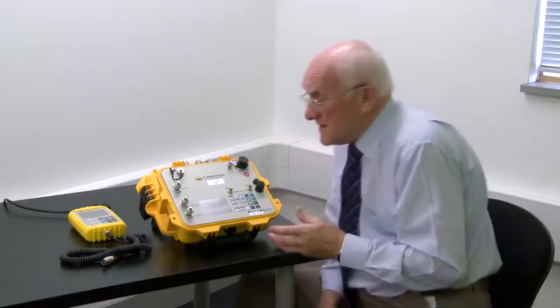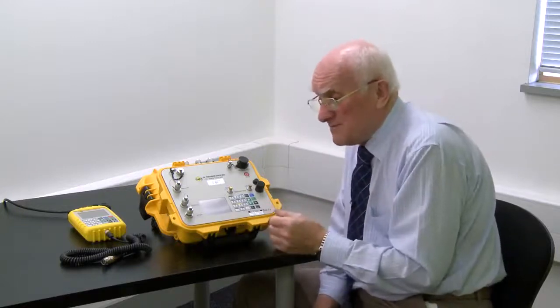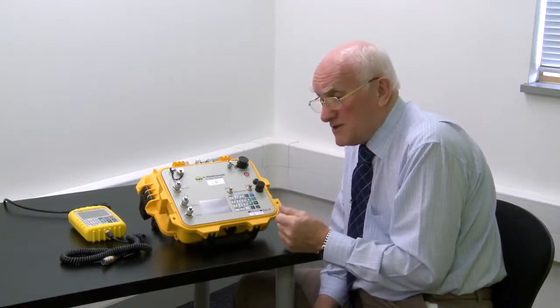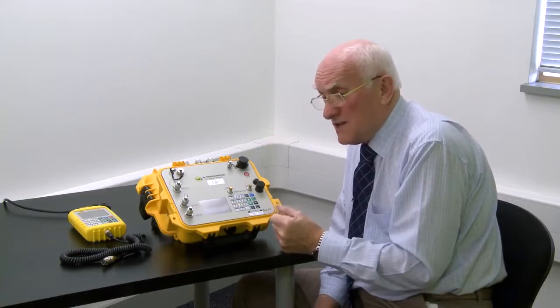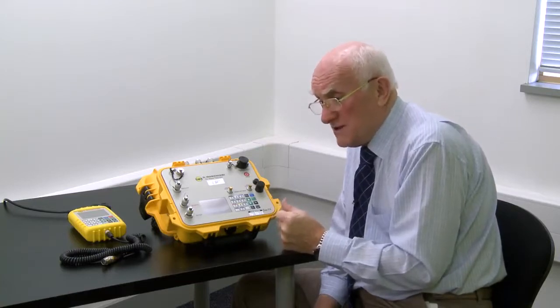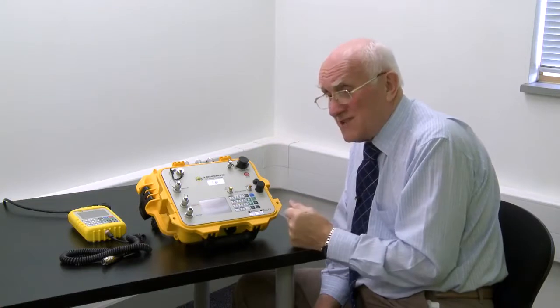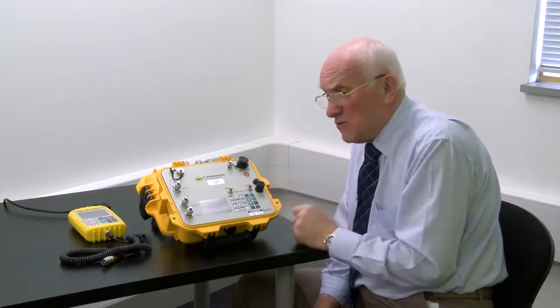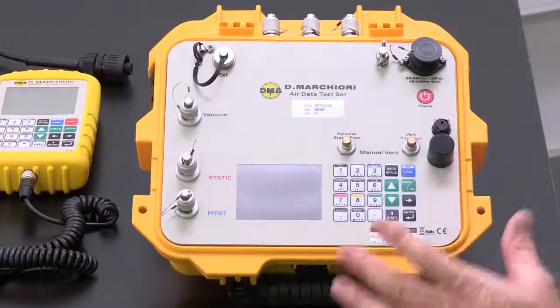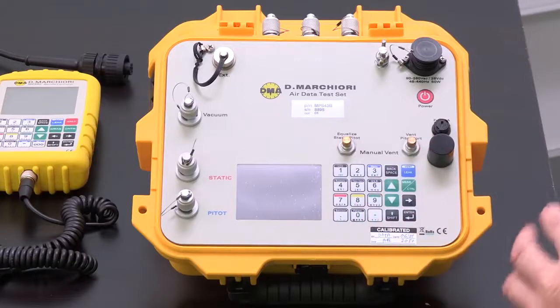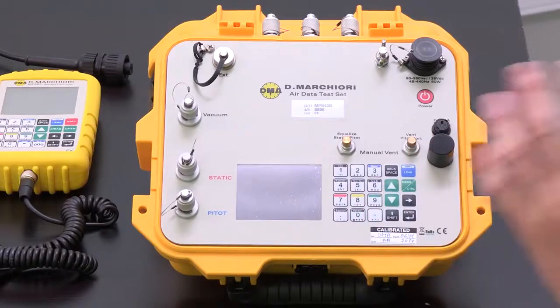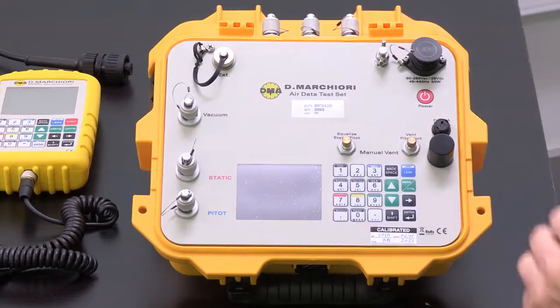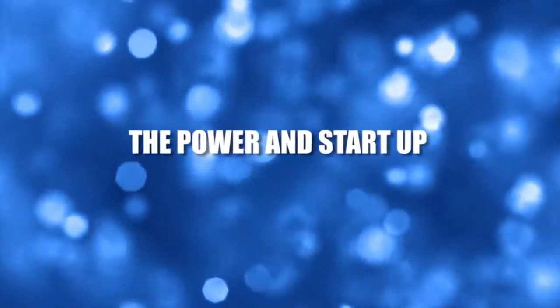The instrument has 2 internal pumps, one vacuum, one pressure, guaranteed for 1500 hours operation. They only run when necessary - they feed a small volume internally to keep those vacuums ready to be used. If you've gone back into measure mode, you don't need the pumps running, so they save life, which is very useful.